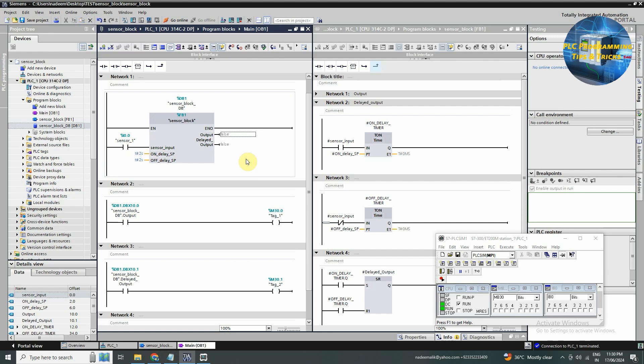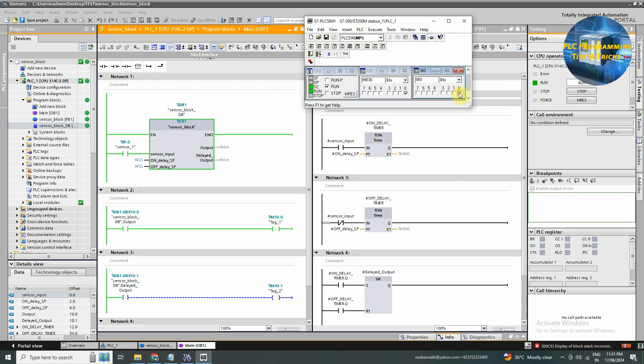Now we will download the program in the PLC and test the ladder logic. As you can see that as the sensor input turns on, the M30.0 bit turns on immediately, but the M30.1 bit turns on after 2 seconds. And as the sensor input goes off, the bit M30.0 turns off immediately, but the bit M30.1 turns off after the delay of 2 seconds. So this is how we can make and use the sensor block. In the next video we will use this sensor block in the ladder logic to understand more practical usage.